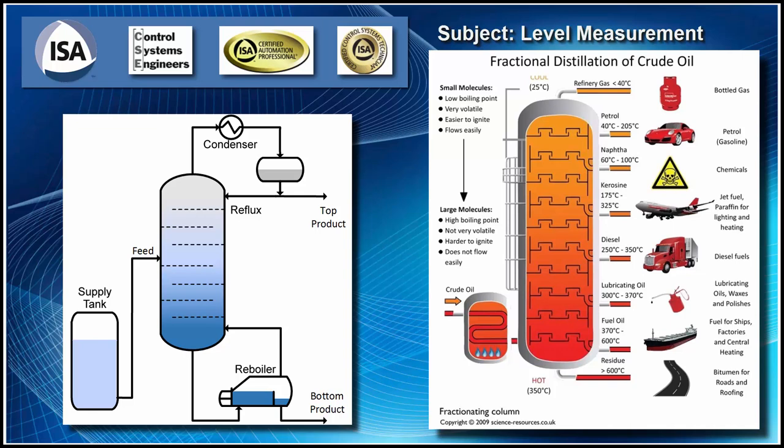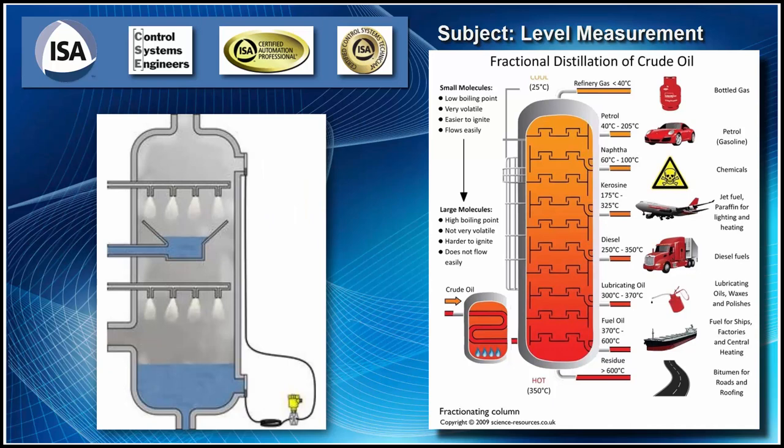So we have to compensate for the pressure with a differential pressure transmitter. The top will have the pressure of the column going onto it, and the bottom also feels pressure of the column. But the bottom feels the pressure of the column plus the weight of the liquid. Since it's a differential pressure transmitter, it'll subtract the gas pressure, vapor pressure, from the low side and the high side. Those will cancel out, and all we're left with is the weight of the liquid. This is how we measure our liquid in a pressurized vessel.